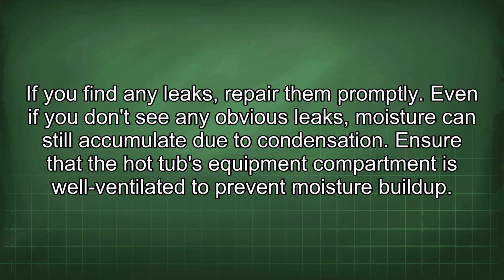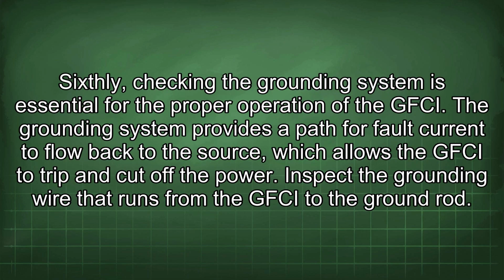Even if you don't see any obvious leaks, moisture can still accumulate due to condensation. Ensure that the hot tub's equipment compartment is well ventilated to prevent moisture buildup. Sixthly, checking the grounding system is essential for the proper operation of the GFCI. The grounding system provides a path for fault current to flow back to the source, which allows the GFCI to trip and cut off the power.